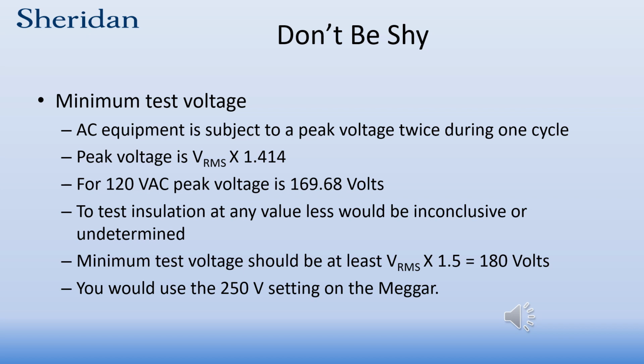To test the insulation with less than that voltage would be inconclusive or undetermined. You're not really testing the insulation. You have to stress it, so it has to be over the standard voltage. As a rule of thumb, the minimum test voltage should be at least 1.5 times the volts RMS, which in this case is 180 volts, higher than V peak. But the Megger doesn't have a 180 volt setting. It has a 250 volt setting, so we'd use the 250 volt setting on the Megger to test this piece of equipment.